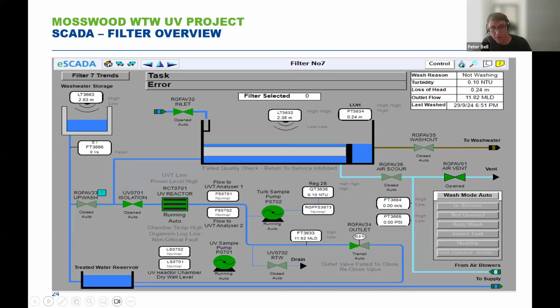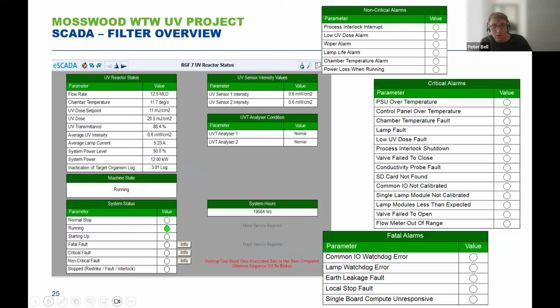And just to show the level of detail of what this started to look like, what we loaded in, we've got a couple of slides to touch on that. So Andy, could you just flip the next slide, please? This is some of the alarms associated with just one filter and the level of detail that we can see. On the left hand side, you can see that we've got flow rate, chamber temperature, UV dose set point, UV dose, UV transmittance, all stuff that is absolutely critical to understand the operation. We then drop down into the system power level, what it's running at, the indication of the log removal, and then what the status is looking like.